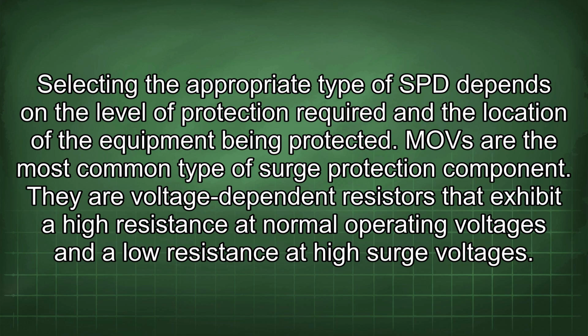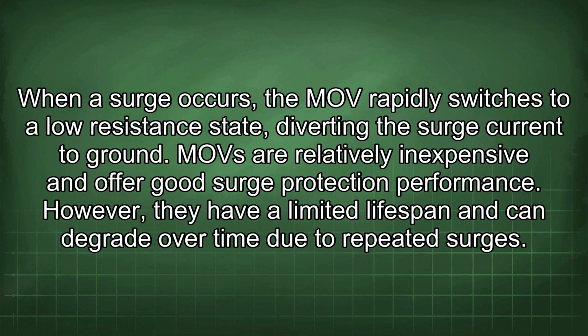MOVs are the most common type of surge protection component. They are voltage-dependent resistors that exhibit a high resistance at normal operating voltages and a low resistance at high surge voltages. When a surge occurs, the MOV rapidly switches to a low resistance state, diverting the surge current to ground. MOVs are relatively inexpensive and offer good surge protection performance. However, they have a limited lifespan and can degrade over time due to repeated surges.